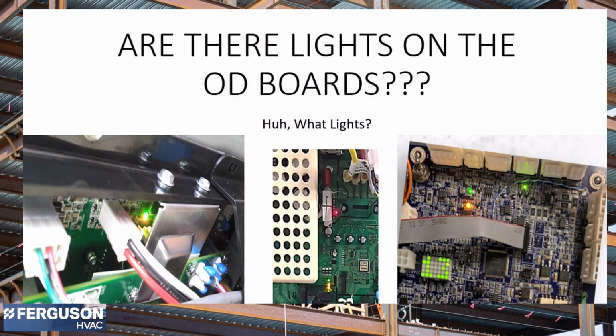Usually when we ask a technician, are there lights on the board, we get the response, huh? What lights? All inverters have LEDs or lights on them that will tell you the status of the equipment. Even the older Greenspeed, the original Greenspeed product that is shown on the left, had a red LED and a green LED hidden behind a little silver plate on the top right of the inverter. So look for the lights and try to determine from the lights what the problem is with the system.